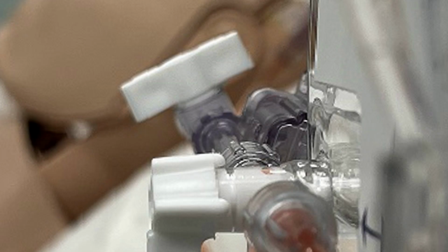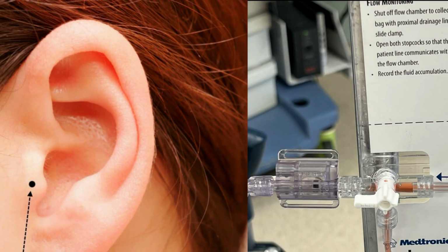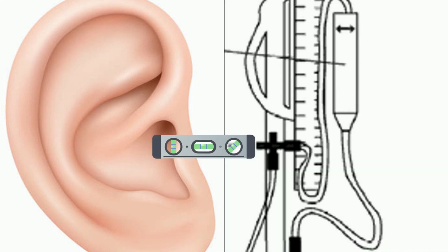To level the EVD, align the transducer with the patient's tragus. Leveling the EVD to the tragus is crucial because this ensures that the pressure readings are accurate and reflect the true intracranial pressure. If the EVD is not properly leveled, the readings could be either falsely elevated or decreased, leading to incorrect clinical decisions and potentially harmful outcomes for the patient.